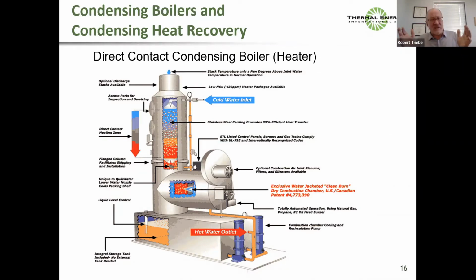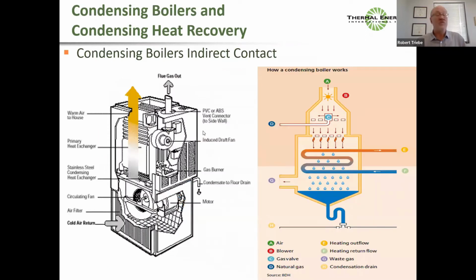So technically speaking, I can call it a few things. It's a wet scrubber with a burner in it. Or it's a burner with a shower being sprayed over it. But in the end, you can get extremely good approach temperatures. Again, I'll talk about that more in the benefits. So this is a hot water heater where the flue gas touches the water. This is a hot water heater where the flue gas does not touch the water. Both of them are used to cool the flue gas to below its dew point so we can get the latent heat.